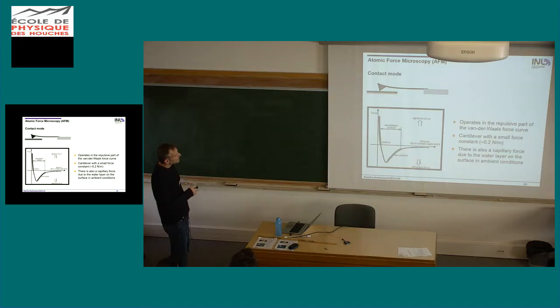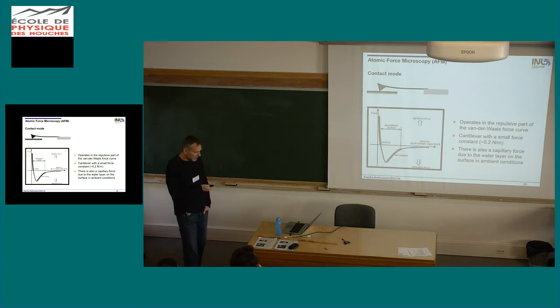So again, in atomic force microscopy, you can measure in contact mode, which means you just press your tip to the surface and then you scan it and you watch how this cantilever moves. And this means you're working in this part of the force distance curve. For this, you use small force constant cantilevers, so you want to use a soft cantilever, not to scratch your sample actually. You want to just feel how it looks, right? Sometimes there are capillary forces, so if you do this in air, of course, depending on how high your humidity is, you possibly have some water layer on your surface, and this leads to capillary forces that might have to be taken into account for the experiment.